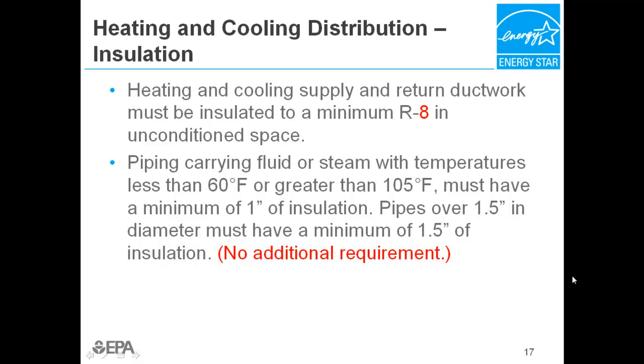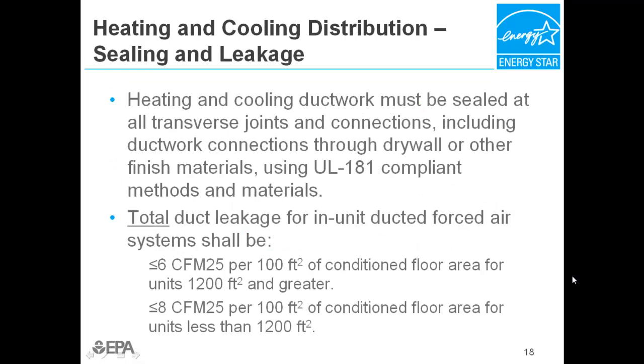Distribution systems, whether hydronic or forced air, have minimum insulation requirements. In the prescriptive path, heating and cooling, supply and return ductwork is increased to a minimum R8 in unconditioned space. Piping insulation remains the same as a prerequisite in the performance path. Ductwork sealing and allowed leakage amounts are also the same as a prerequisite in the performance path. Duct sealing must utilize UL 181 compliant methods and materials, and total duct leakage amounts must be tested to be less than either 6 or 8 CFM per 100 square feet of conditioned floor area, depending on the size of the apartment.